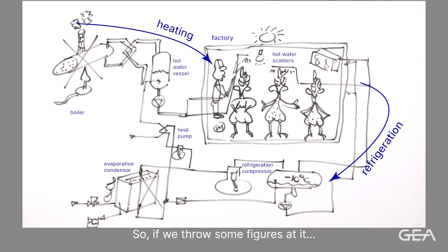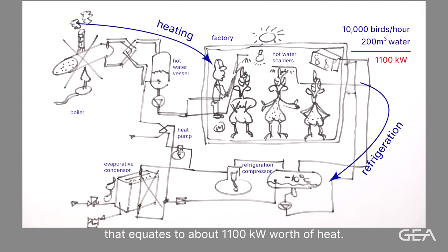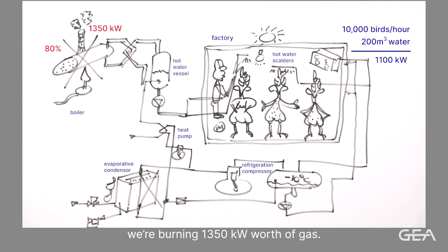So if we throw some figures at it, 10,000 birds per hour and circa 200 cubic metres for wash down at night time because the hygiene guys go wild, that equates to about 1,100 kilowatts worth of heat. If we then say that we're doing it with an 80% efficient boiler, we're burning 1,350 kilowatts worth of gas. The cost of gas is about 2 cents per kilowatt. So that costs you around about 250,000 euros a year to generate the heat.